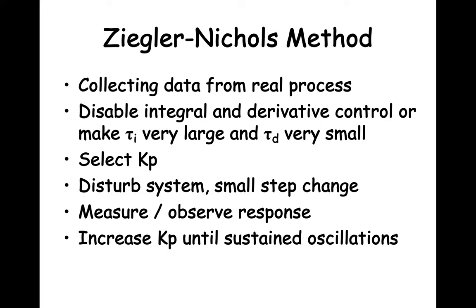To collect data for the Ziegler-Nichols method, the integral control and the derivative control parts of the controller are disabled. If the integral part cannot be disabled, set the value for tau i to some very large or maximum value. If the derivative control cannot be disabled, set tau d to a very small or minimum value. Then select a Kp value, disturb the system with a small step change, and record the process response. If you don't get sustained oscillations, increase Kp and disturb the process again. Repeat until the process output is a sustained oscillation.